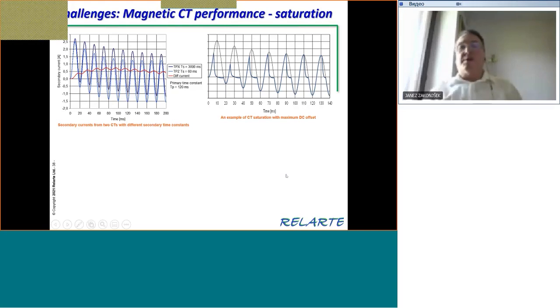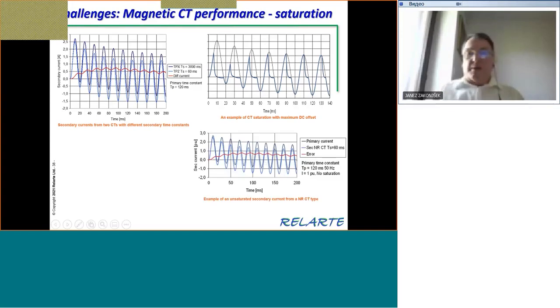So that was one of the very interesting things which we have to consider today. And what we have here is, for example, unsaturated secondary current from a non-remanent CT type. So even if it is non-remanent CT, it can go into saturation. But here it's unsaturated. So it shows, let's say, the difference, which I show also here.